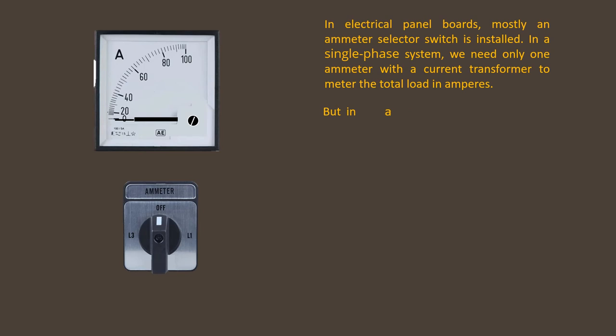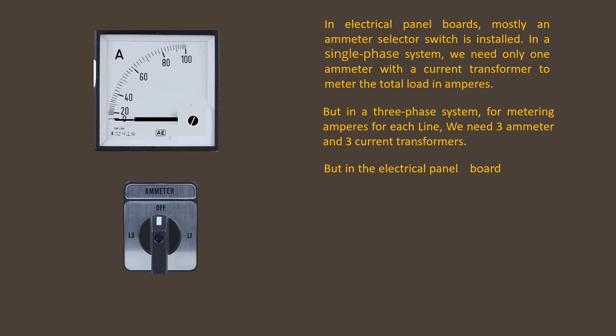But in a three phase system, for metering amperes for each line, we need three ammeters and three current transformers. But in the electrical panel board, we can do this with only one ammeter or ampere meter by using the ammeter selector switch.